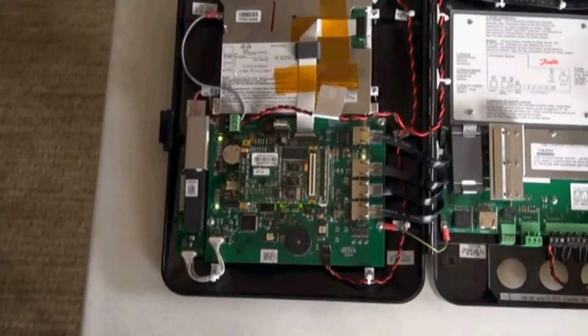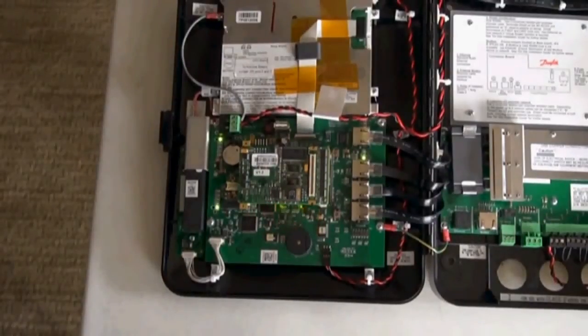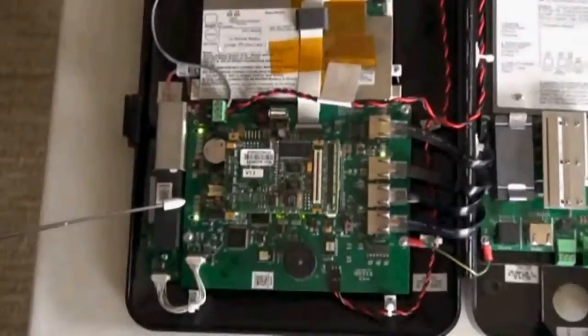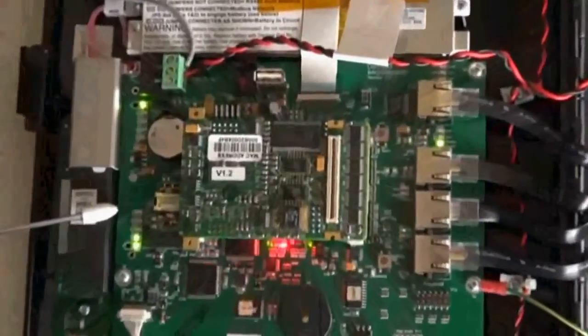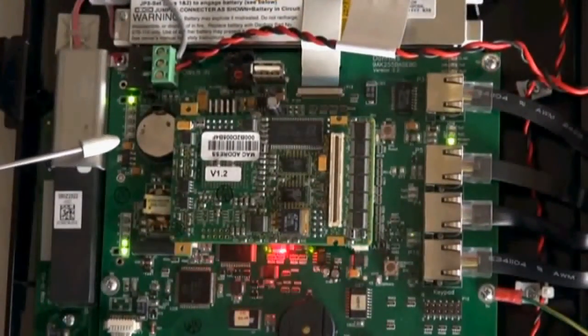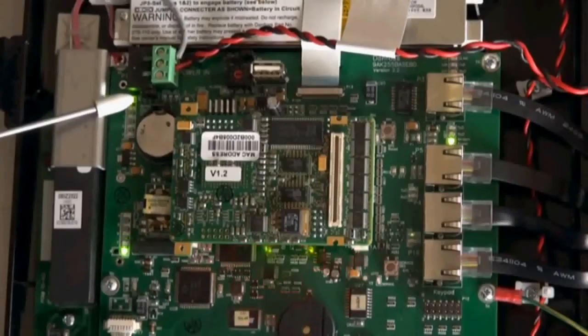Let's take a look inside the details of the AK2-55 controller from Danfoss. First we'll look at the baseboard and CPU combination. Here you'll find the 3-volt lithium battery. Just above the battery is the battery jumper. The board is marked with 3 terminals, 1, 2, and 3. To retain the settings in the controller, the battery jumper must be across pins 1 and 2.